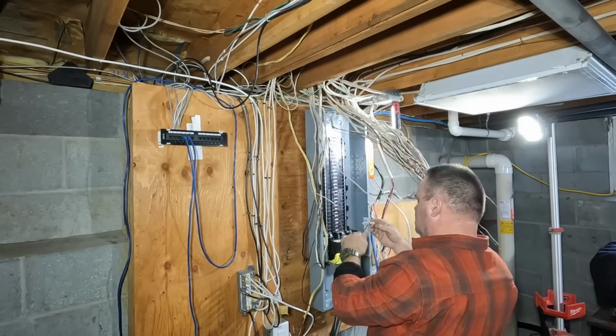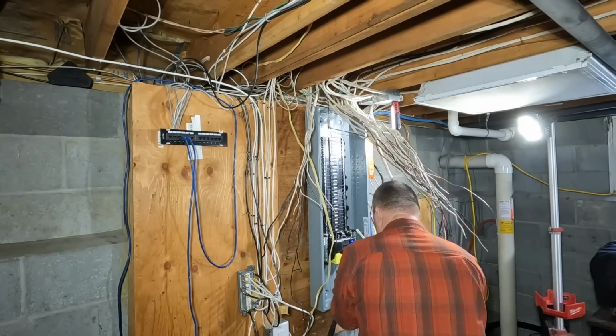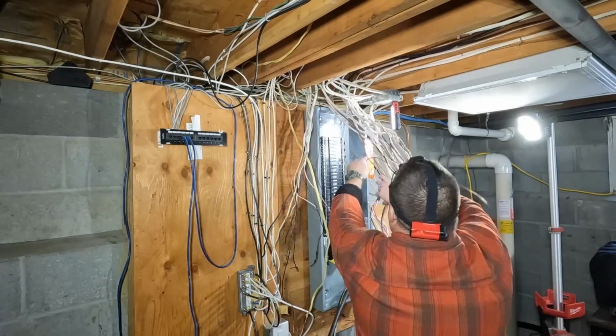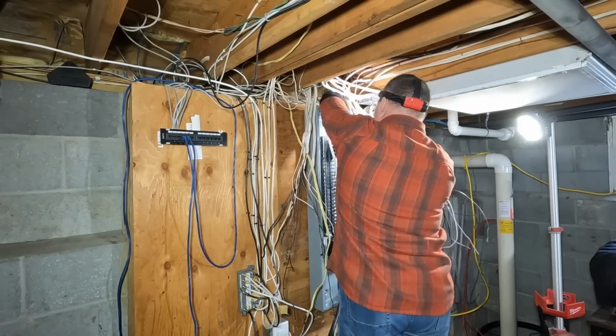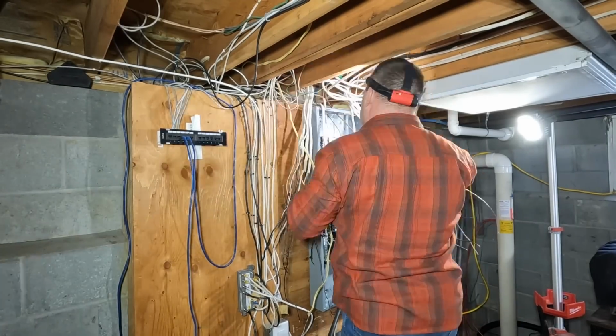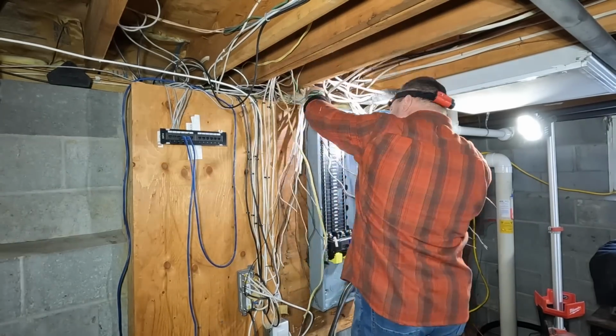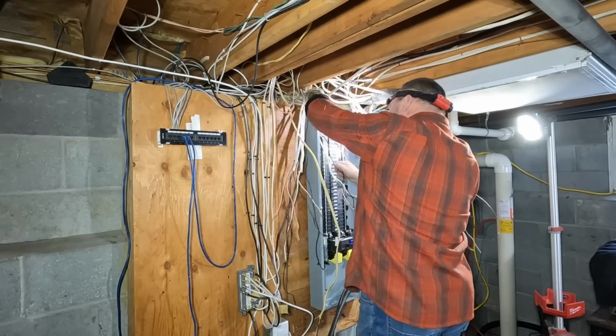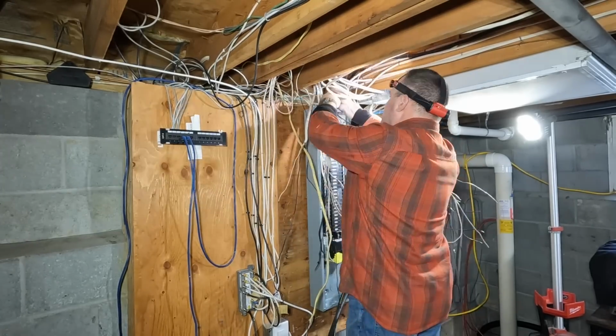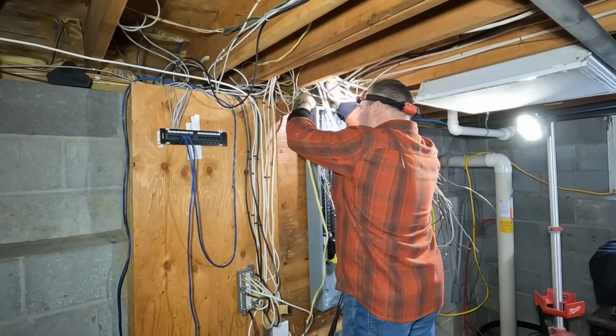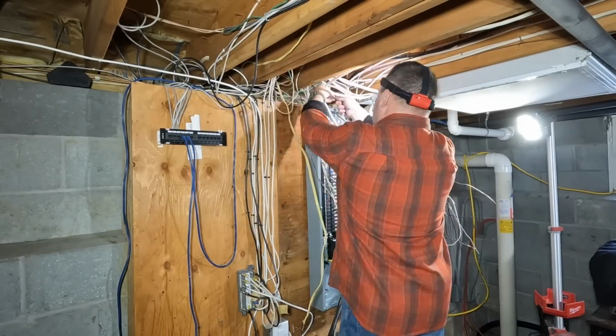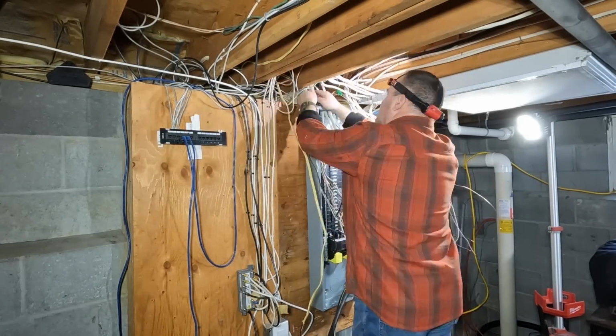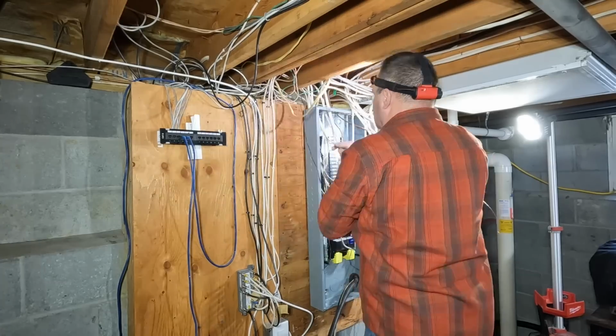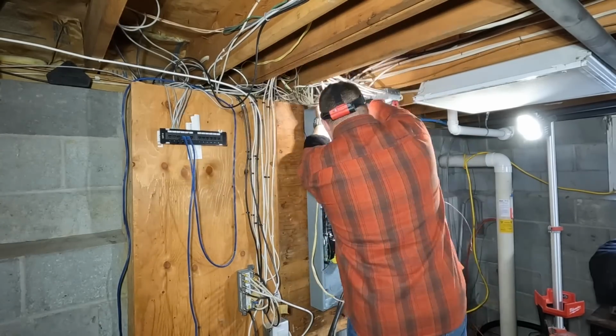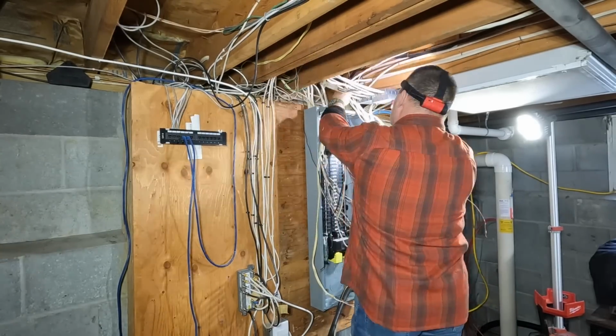Okay, so now we're all set, and I got a lot of wires here. Fortunately, most of them are long enough, but one of the issues I do have is I need to put in a couple of ground buses on either side of the panel here for some of the neutrals and equipment grounds that won't reach the terminals that come with the panel, because the main circuit breaker is at the bottom, and that's where those terminals are at. So we're going to wind up putting in a couple of terminal bars and do some number 4 copper jumpers between the new bars and the equipment bus for the terminals down below.